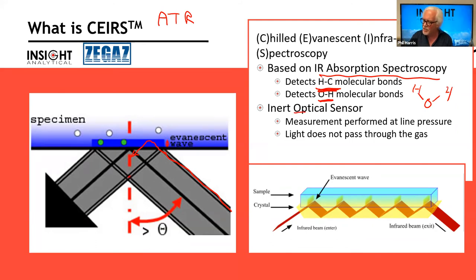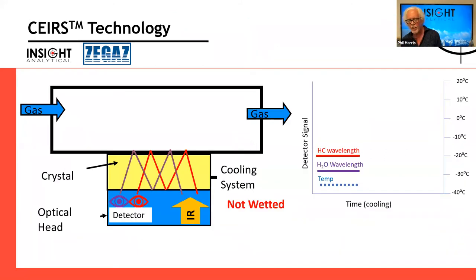So this inert optical sensor, this crystal that doesn't react with anything, is put in there at line pressure, and the light doesn't even have to go through and touch the gas. It touches whatever that little evanescent wave sees on the surface. So let's think about what happens then. We take this crystal and we shoot two beams of light through it. Two different colors. One of those colors happens to be a color that the hydrocarbons want to interact with. And the other color of light, and I'm simplifying this a bit, there's actually more than just two wavelengths being used, is something that water is going to interact with. So the light bounces across the crystal and makes its way over to detectors.